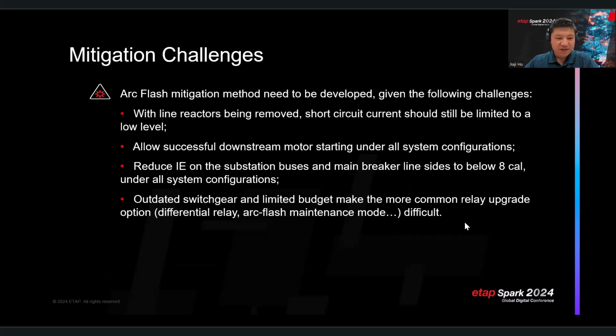The fourth one we need to consider is that this is an outdated switchgear with very old equipment. And with a limited budget, it's not very easy to just recommend more common relay upgrade options like differential relay installation or switching to a microprocessor relay with arc flash maintenance mode. So here we really need a more customized solution to be offered to the client. So from here, I'm gonna pass to my colleague Aditya to present you our solution for this condition.